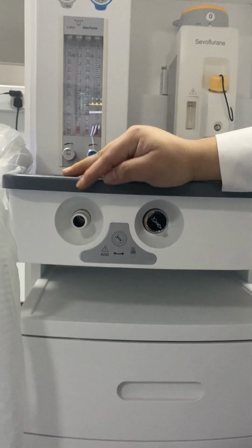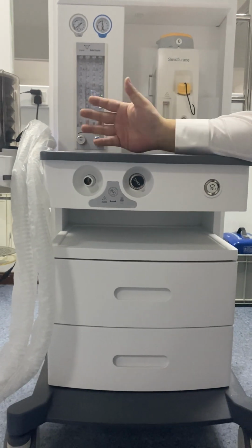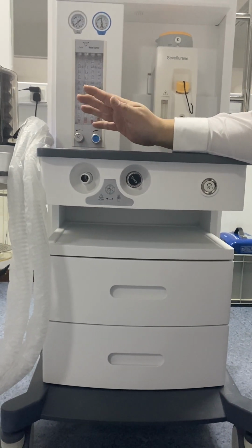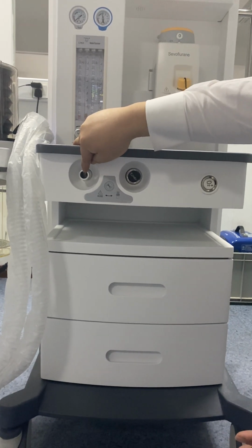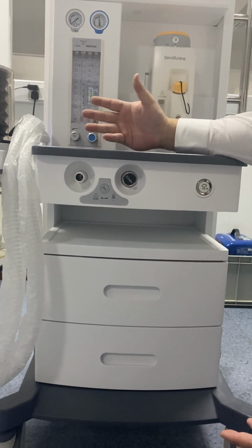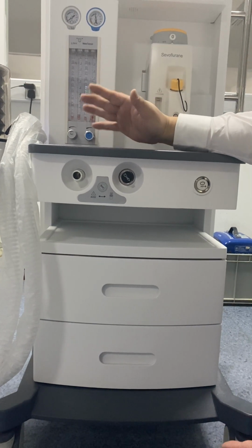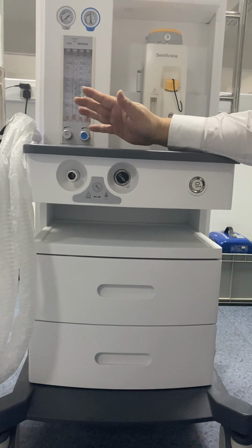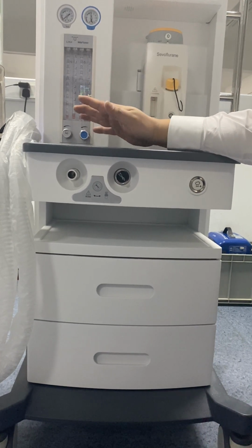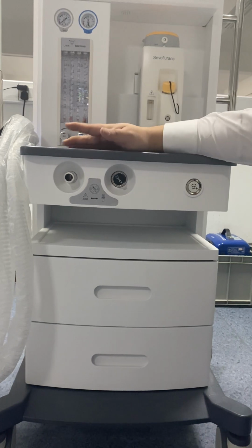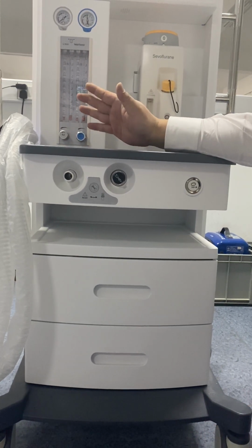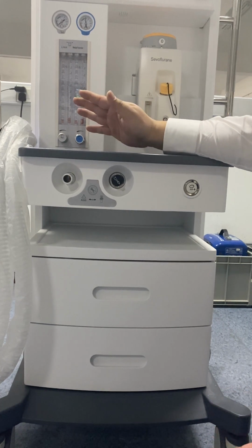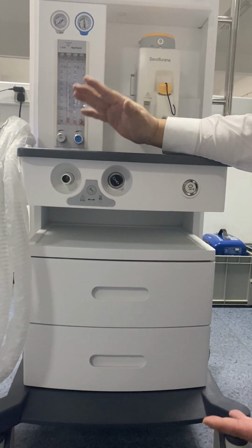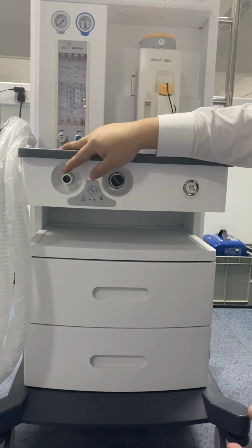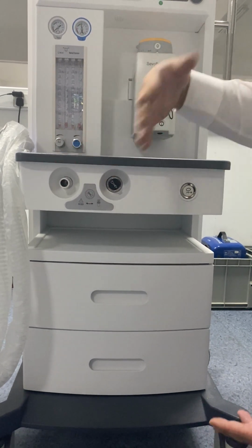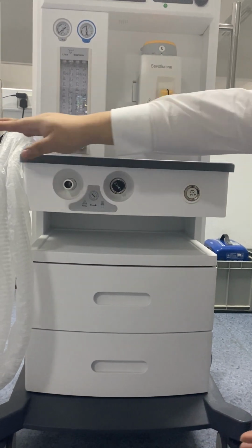The first function of the ACGO is that after the operation, when we want the patient to recover soon, we can connect the ACGO port with the pipeline and let the patient breathe pure oxygen, so they recover in the next 5 or 10 minutes. So it makes their recovery faster. The second use is, for example, in an emergency situation when a patient comes to the hospital and needs an operation immediately, we don't have time to test whether they have an infectious disease. Then we can connect the pipeline to the ACGO port for the operation, so that it will never influence the main pipeline.